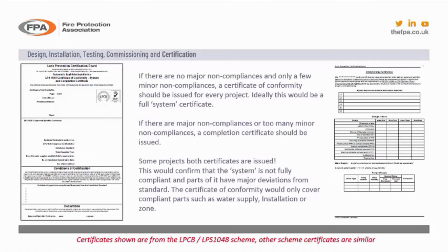Now, what's changed over the last few years in the industry is you may have a sprinkler system for a building, and you may issue various different certificates. So you may get a fully compliant water supply. You may get a certificate for just the water supply. You may have a fully compliant installation. You may get a certificate for the installation. Or take a shopping centre, for instance, or an office block where it's been split into zones or shop units or floor levels. You may get a certificate of conformity for the zone if that complies, but you may have sprinkler mains running in unprotected areas, and if the loss of these would lose the system, you don't get a full Shangri-La certificate as such. You don't get the system certificate, you get bits for the others, and then obviously for the system where it's non-compliant, you'll be looking at completion certificates.